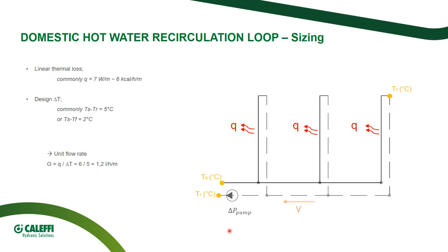So the sizing of a recirculating loop is based on a couple of fundamental parameters. One is the linear thermal loss of the system, which depends on the pipe material and on the insulation of the whole building. From the literature, we know that an average good reference value can be 7 watts per meter of length. And the other parameter that the design is usually required to fix is the delta T between supply and return.